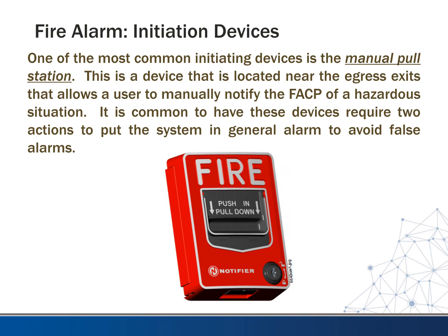One of the most common initiating devices is the manual pull station. This is a device located near egress exits that allows a user to manually notify the fire alarm control panel of a hazardous situation. We usually put these where you exit stairwells, near elevators, and at all egress exits. That way, if someone is fleeing the building, they can pull the alarm in case it hasn't already been signaled by another detector.